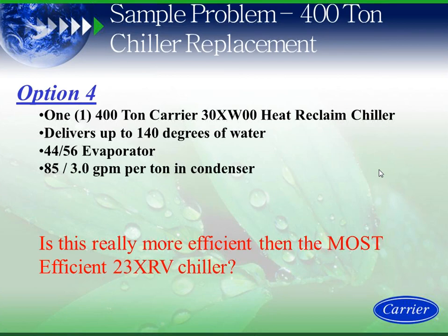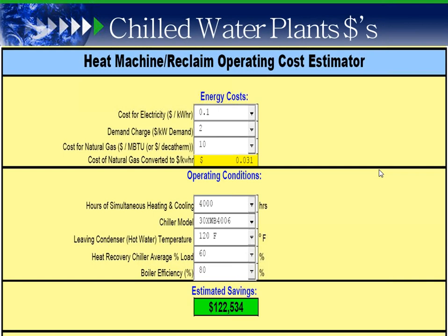What we can do is we could do option 4, which is our one Carrier 400-ton Carrier 30XW heat reclaim chiller, dual compressor machine, can deliver up to 140 degrees of water, same conditions on the evaporator and condenser, and is it really more efficient than the most efficient 23XRV chiller in the industry?